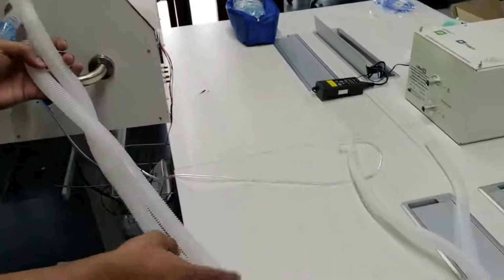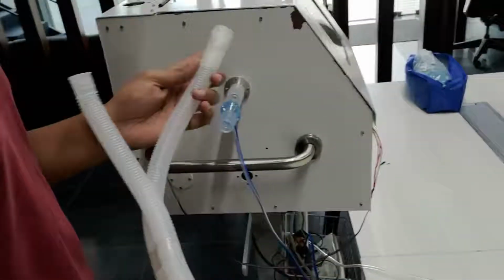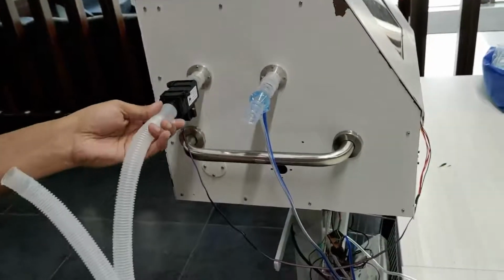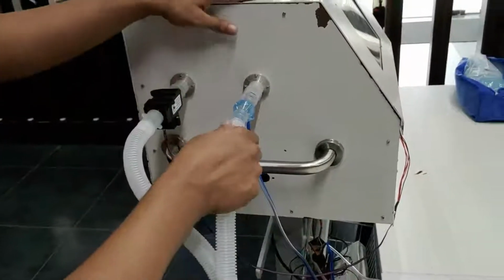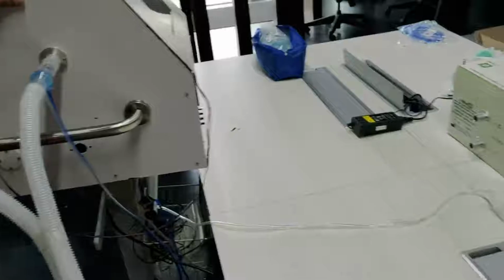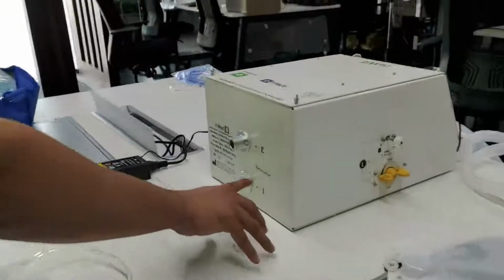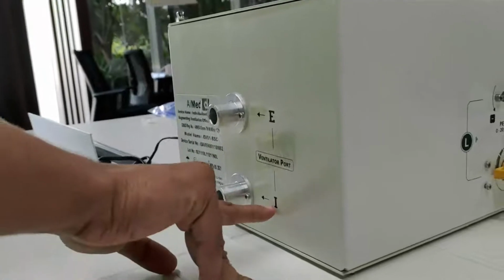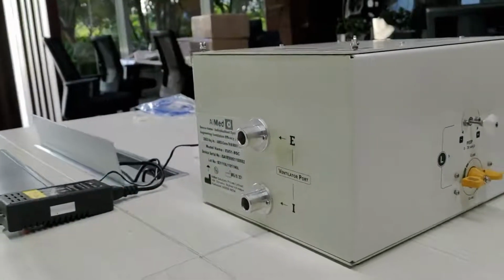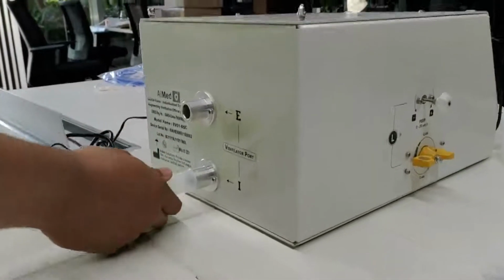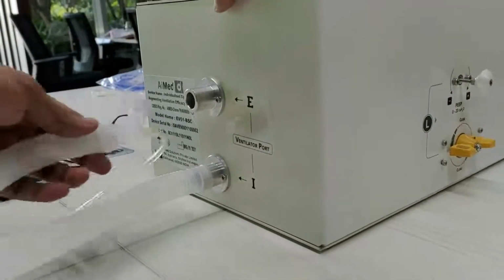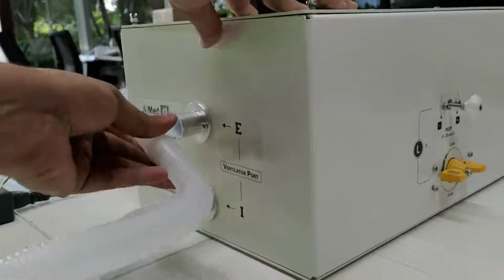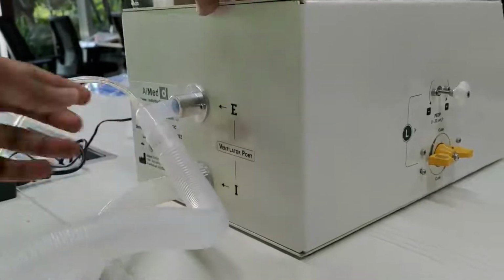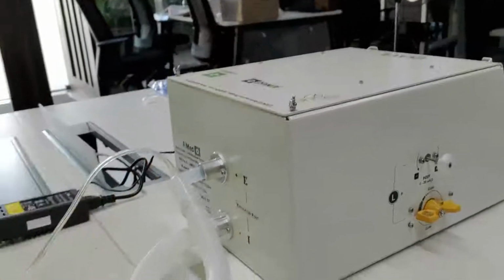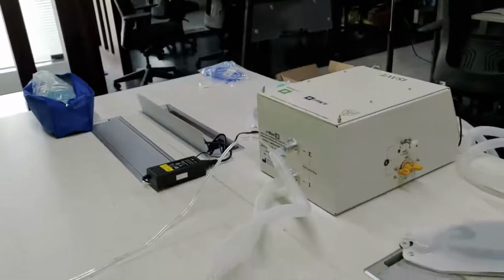While it's booting up, let's connect the ventilator to the iSAVE. We'll do this like we do normally. On the ventilator side, we connect the inspiration to the inspiration and the expiration to the expiration, as we normally would. On the iSAVE, you can see it's marked for the ventilator port I and E. This is the inspiration port, this is the expiration port. We'll connect the inspiration tube from the ventilator to the iSAVE, and similarly connect the expiration port from the ventilator to the iSAVE. You can connect your pressure sensing or anything like that on that port if it's external.